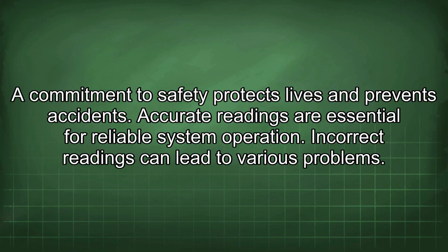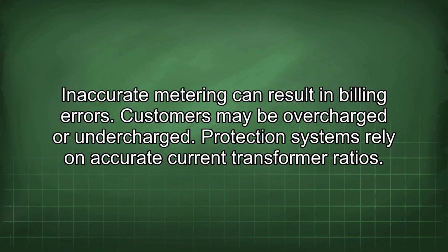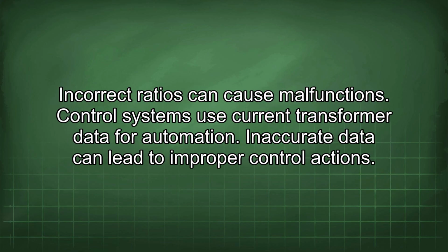Accurate readings are essential for reliable system operation. Incorrect readings can lead to various problems. Inaccurate metering can result in billing errors. Customers may be overcharged or undercharged. Protection systems rely on accurate current transformer ratios. Incorrect ratios can cause malfunctions. Control systems use current transformer data for automation. Inaccurate data can lead to improper control actions.